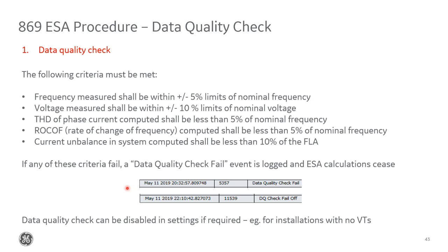In terms of the actual ESA algorithm, here's the steps that we take broken down. So the first thing we do is a data quality check to make sure we're monitoring a valid signal. We check that the frequency is within plus or minus 5% of nominal, that the voltage is within 10% of nominal. We look at the harmonic distortion to make sure it's not in excess of 5%, that the frequency is not rapidly changing, and that the current imbalance is less than 10%.